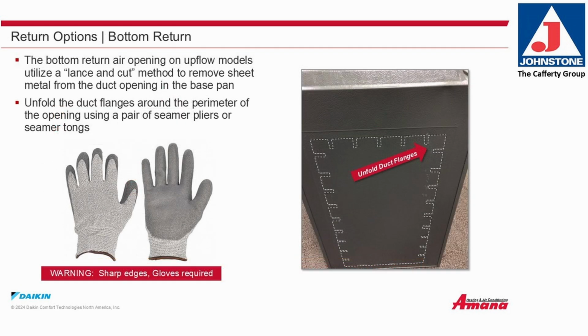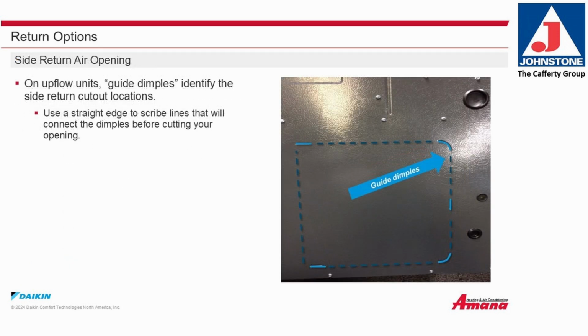Return options. Bottom return. The bottom return air opening on upflow models utilizes a lance and cut method to remove the sheet metal from the duct opening in the base pan. Unfold the duct flanges around the perimeter of the opening using a pair of seamer pliers or seamer tongs. Warning: sharp edges. Gloves are required. Return options. Side return opening. On upflow units, guide dimples identify the side return cutout locations. Use a straight edge to scribe lines that will connect the dimples before cutting your opening.